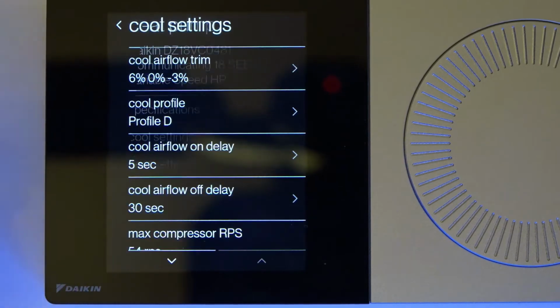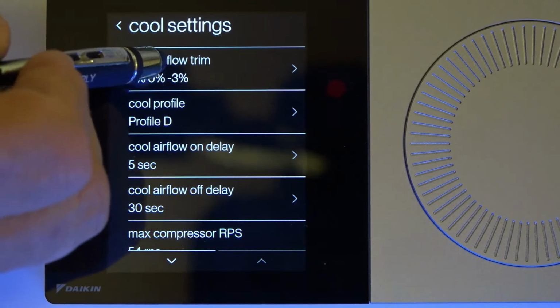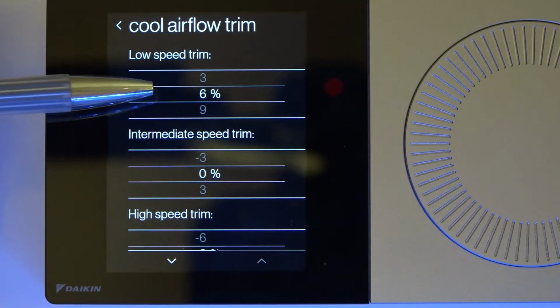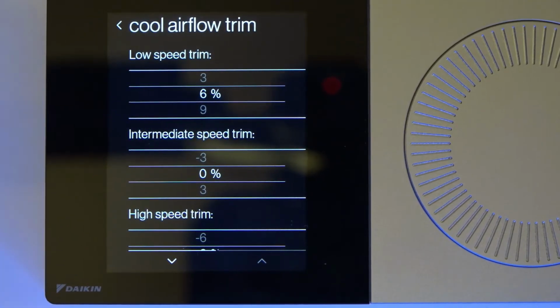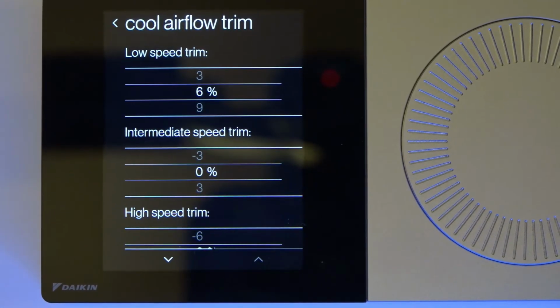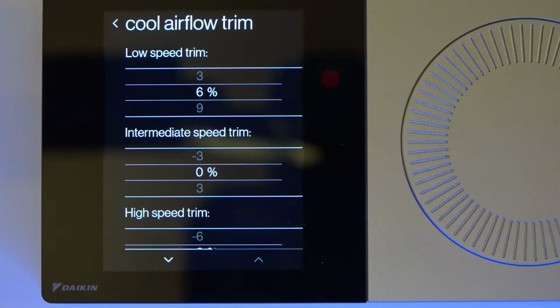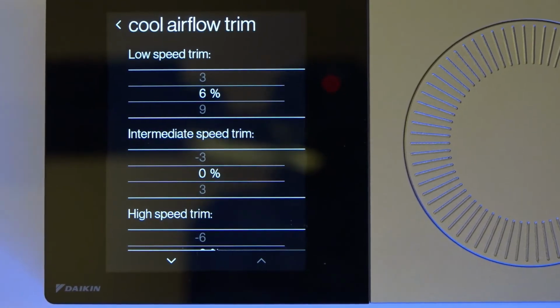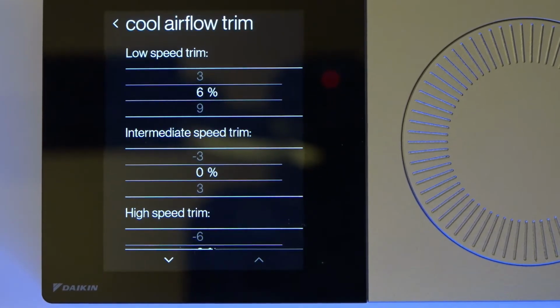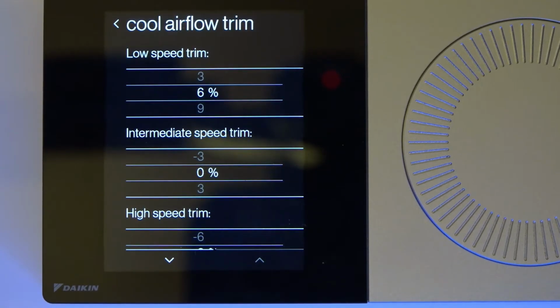So let's back up out of specifications. One of the things I like to do is go to cool settings. Cool air flow trim. Now in the low range, I'll plus up my CFM. I give it a boost in the low range of compressor operation, either 5 to 6%. That does a better job of pressurizing my duct system when I'm at a low compressor output. And it also will change the temperature of my evaporator coil. Since I'm running a higher amount of air across the coil, my coil runs 1 to 2 degrees warmer. So that'll extend out a cooling cycle on a mild day. That way I get a little bit longer dehumidification out of the system.